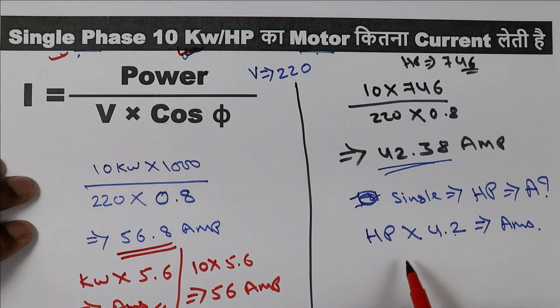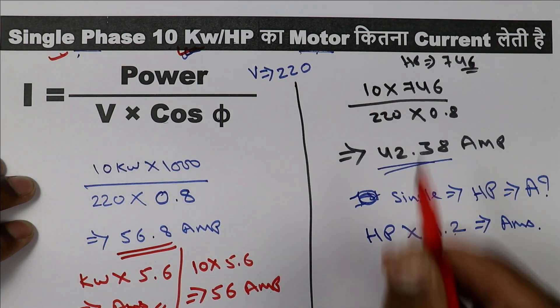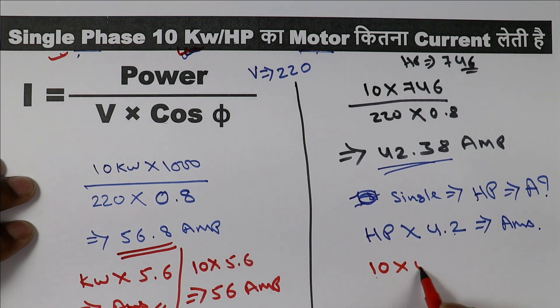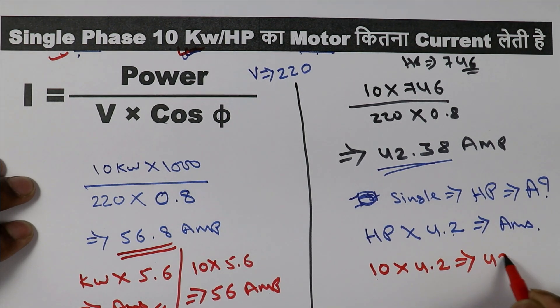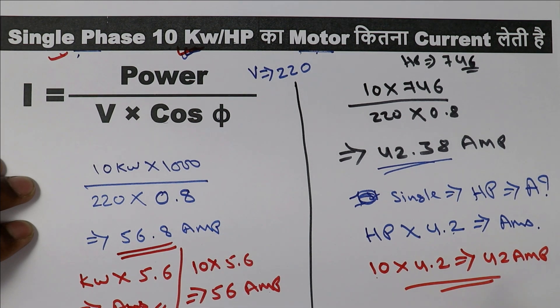For the short trick for a single-phase horsepower motor, simply multiply horsepower by 4.2. For a 10 HP motor, 10 multiplied by 4.2 gives 42 ampere. You can see here also we got almost the same answer as the exact calculation of 42.38 ampere.